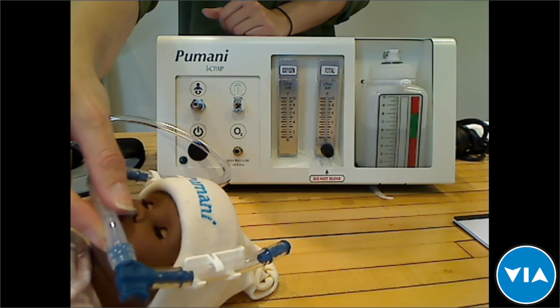Right. Yes, and just to speak on the cannula too, many of you who are familiar with CPAP know that the tightness of the prongs in the nostrils is really important. There really shouldn't be leaks at the nostrils, so the prongs should be tight in the nostrils, and the 6 different prong sizes that we provide allow you to adjust the size as you need to. So we've also seen in some cases, let's say a baby starts on size 2 prong, but over several days their nostrils might start to slightly expand and they start to have some leak at the nostrils, and then you can upgrade to a size 3 or size 4 prong. So that's commonly done in the US as well, and you can do that with our set of prongs as well.